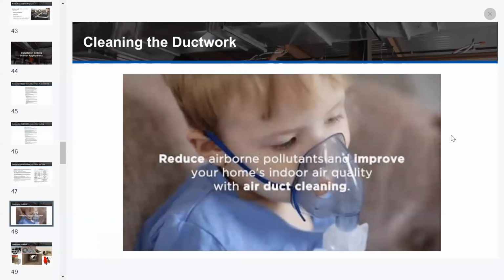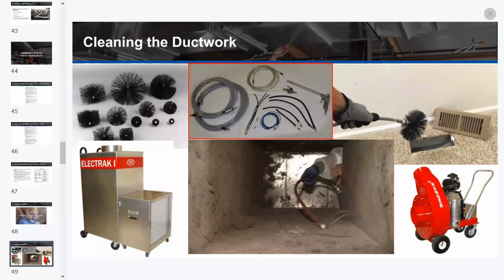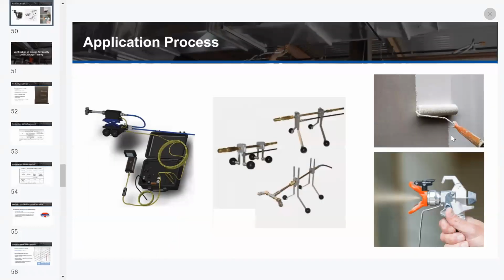And as we all know, next slide, there is a large group called NADCA, the National Air Duct Cleaners Association, that do duct cleaning. And it's key that if you're going to do any kind of interior restoration or any kind of interior work on a duct system, ideally you should get it cleaned. Here you can see a small sampling of some of the brushing, air whipping, and collection tools that are used to clean ductwork. Once again, there's a whole industry of NADCA that's focused on that. In a lot of cases they will use a HEPA contact vac, where they physically vacuum the surface of the duct system to remove any of the items there.